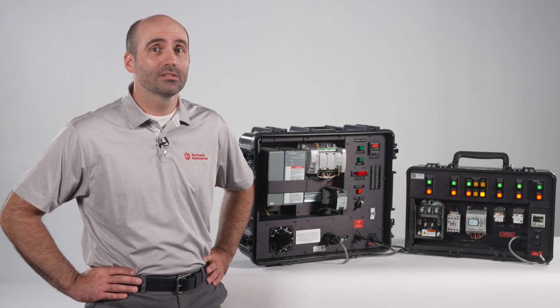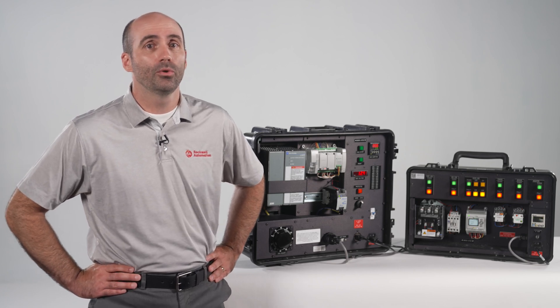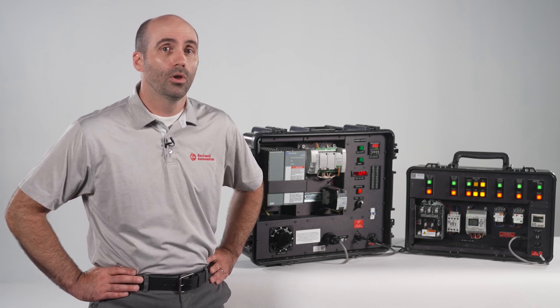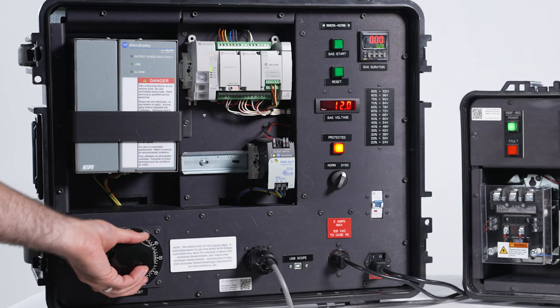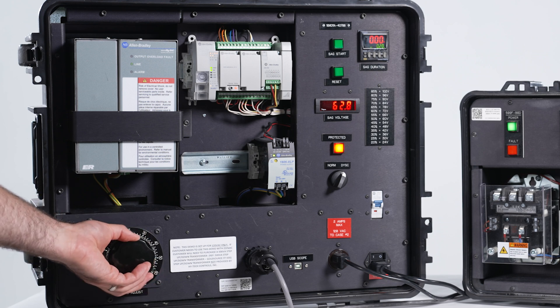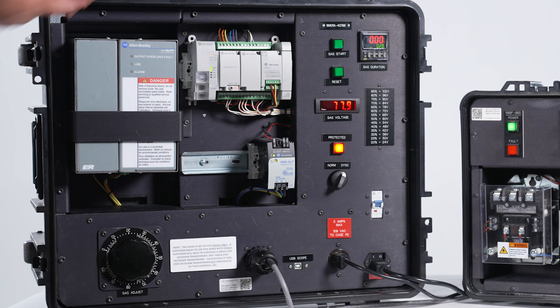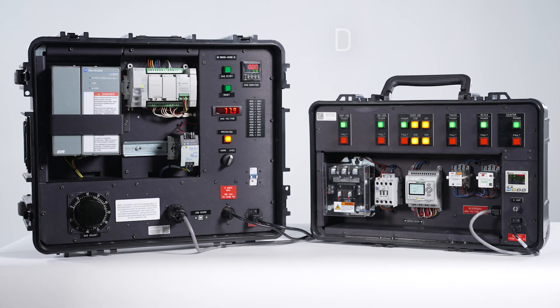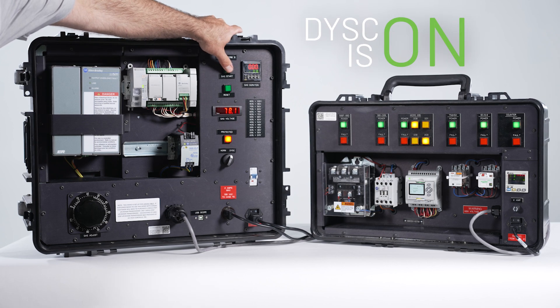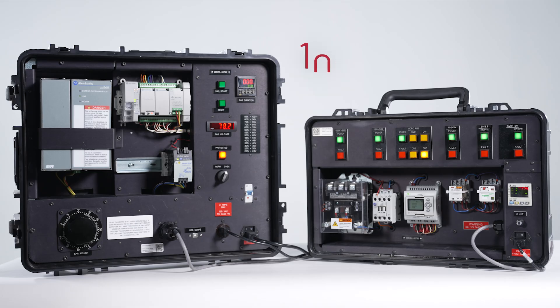Next, we'll add the DISC dynamic voltage sag corrector and test its capabilities to overcome the voltage sags previously simulated. We'll online the DISC for protection. Let's turn the DISC on. Now we'll configure the first scenario again — a 65% remaining voltage sag for 100 milliseconds. Let's run the simulation. With a voltage drop to 78 volts for 100 milliseconds, none of the on-site equipment tripped.